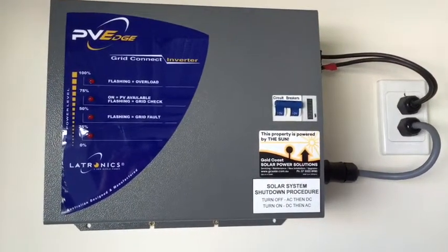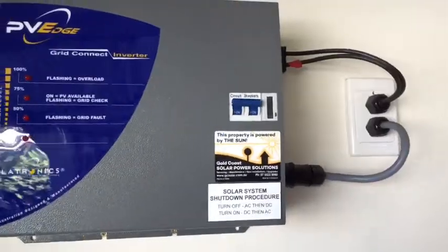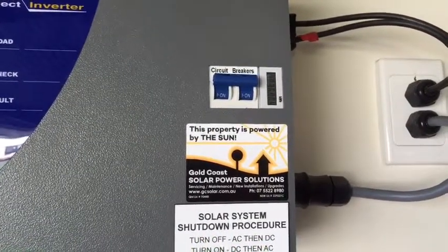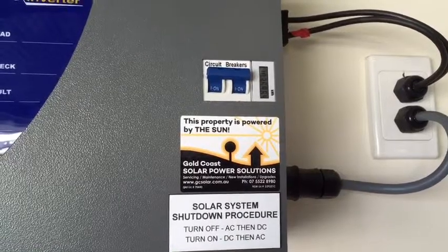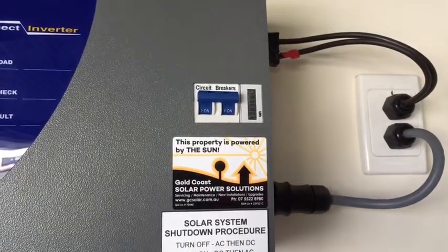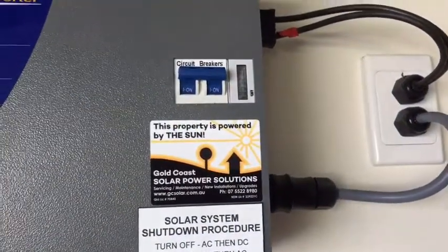If you're an electrician, the best thing to do is actually check that the inverter has DC power coming into it, and always check that this circuit breaker here is in the on position. This is one thing we've commonly seen with these Latronics inverters — the circuit breakers actually fail. Latronics are a good brand, but they've used a cheap DC circuit breaker built into the inverter which tends to fail after a while.